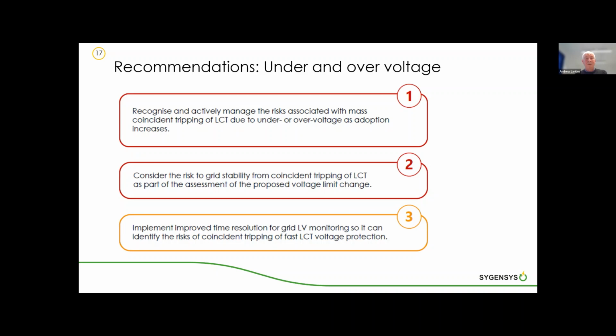So power converter connected technologies generally will include under and over voltage protection, and the fault ride-through requirements for those are not clearly defined in an explicit manner that gives great consideration to the 100 gigawatts of load that may be appearing and the risk of ending up with coincidence tripping of load.